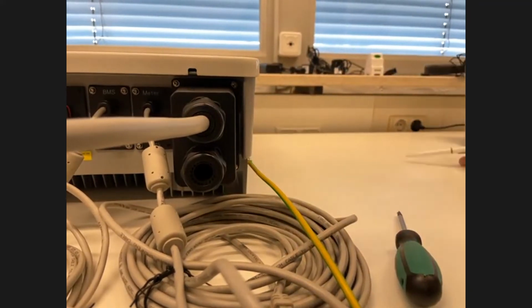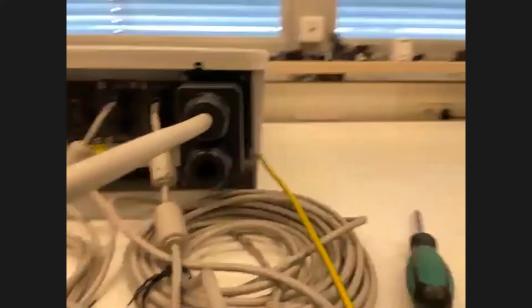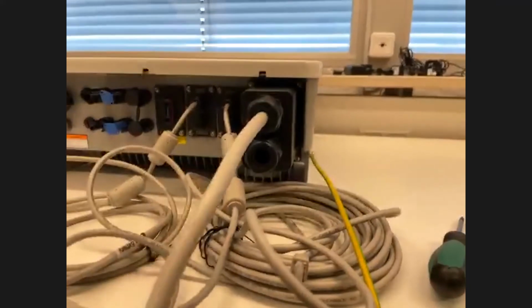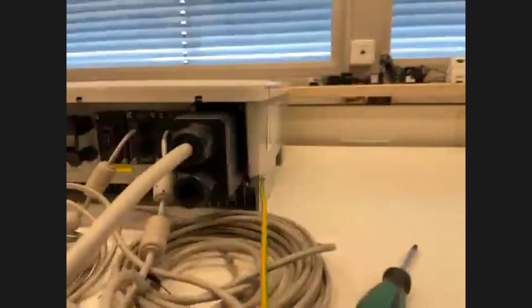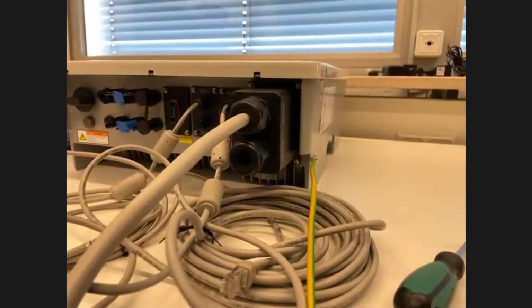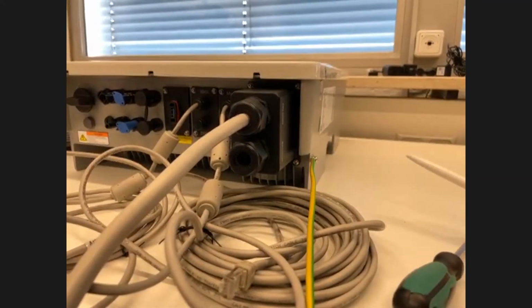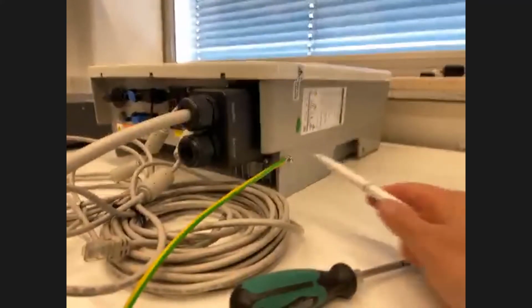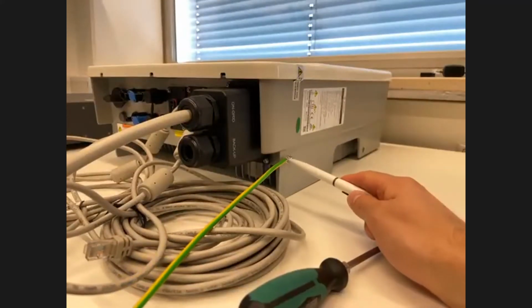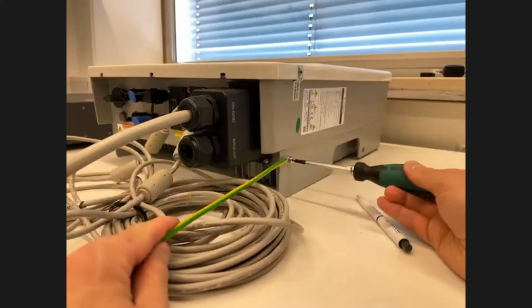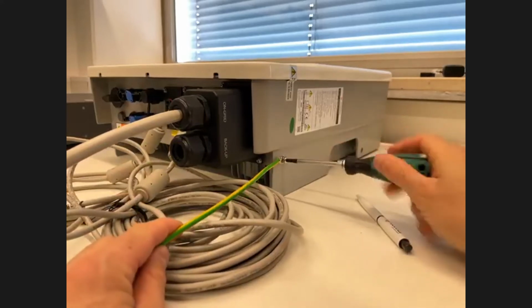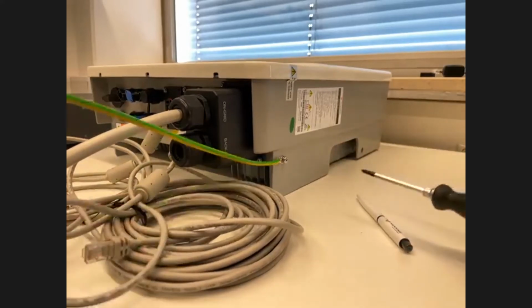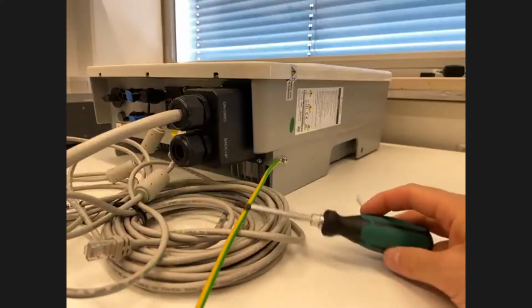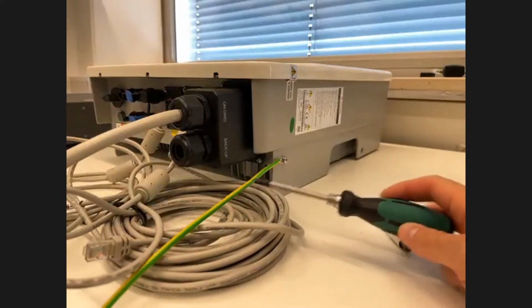So firstly, you should connect the DC side. Before doing that, it's really important that you connect here on the side the grounding cable. This is quite easy, it's just a screw here, you just attach it. Make sure you have the correct size of this cable.